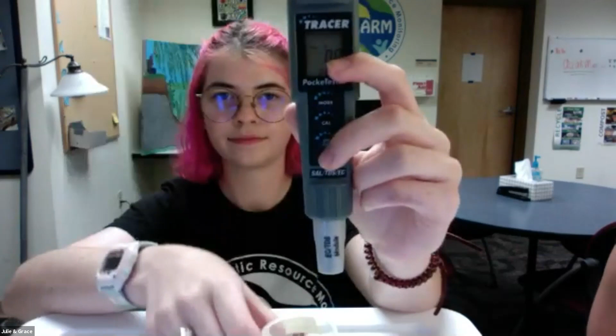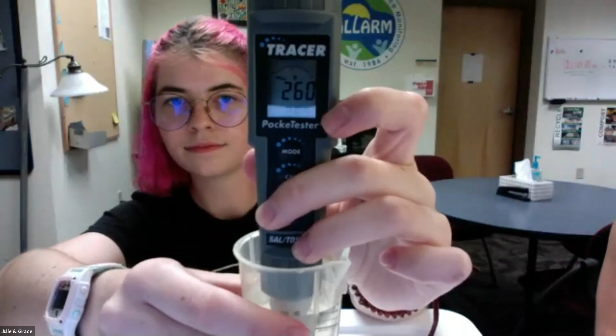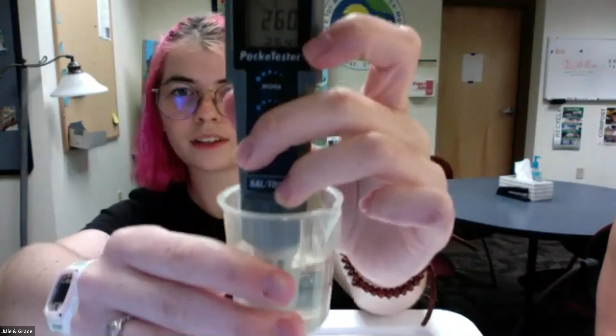Awesome. Excellent. So once you are in degrees Celsius, you are ready to place the electrode in the stream, or in this case, the water sample, and allow the temperature reading to stabilize. The temperature reading is the smaller number at the bottom right of the screen. And there is a nice diagram on page 10 to show you exactly where this is on the screen of your meter. Remember that the larger number is the conductivity reading, and this will be measured during the post-stream section, so you do not need to worry about that now.